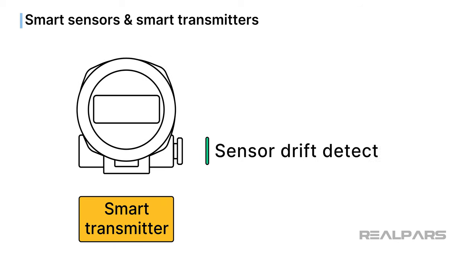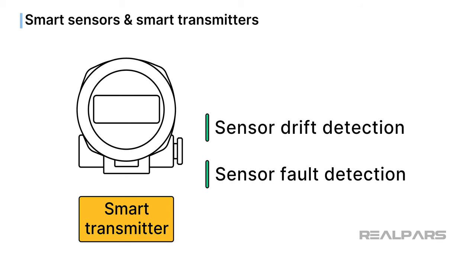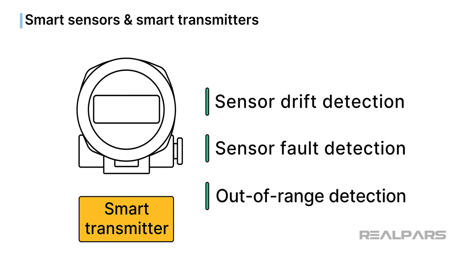Sensor drift detection looks for a gradual change in the sensor output that deviates from the expected behavior over time, thus predicting when calibration or maintenance is required. Sensor fault detection recognizes faults such as sensor damage, open circuits, or short circuits in the sensor circuit. Out-of-range detection monitors if the sensor reading falls outside predetermined ranges. Sensor health detection helps to predict sensor degradation by tracking the overall health of the sensor by analyzing various parameters.